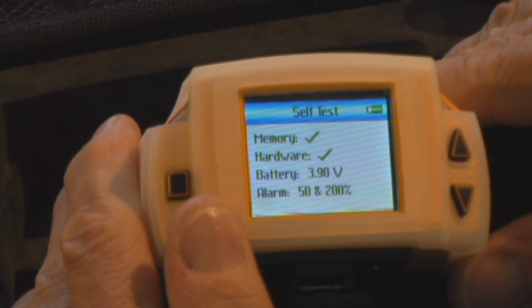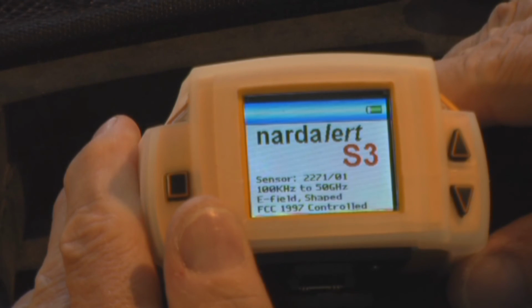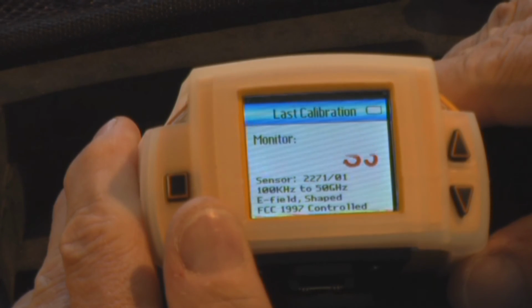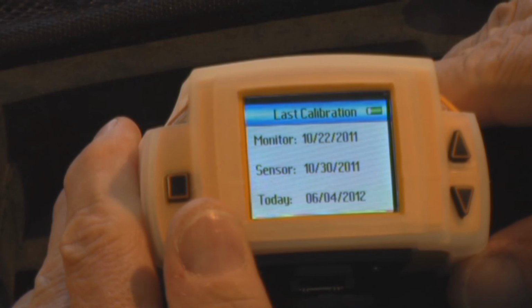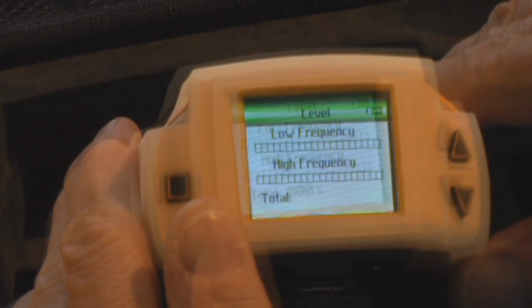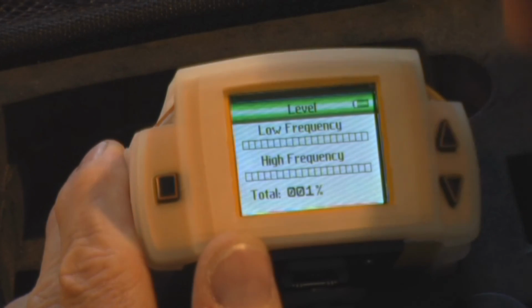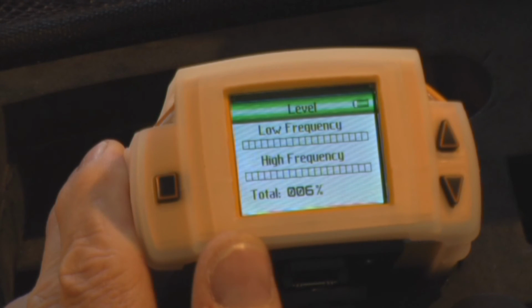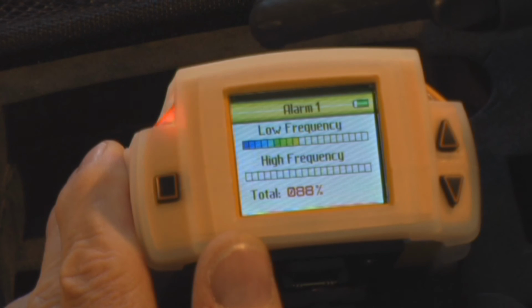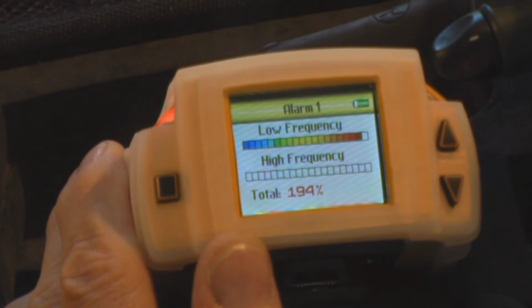The sensor installed in this mainframe is a 2271 that is used for frequencies between 100 kHz and 50 GHz and shaped to the FCC control limit. The separation between the low frequency and high frequency sensors occurs somewhere around 1000 MHz. This can be an extremely useful feature to help identify the actual RF emitter sources causing alarms at a site.